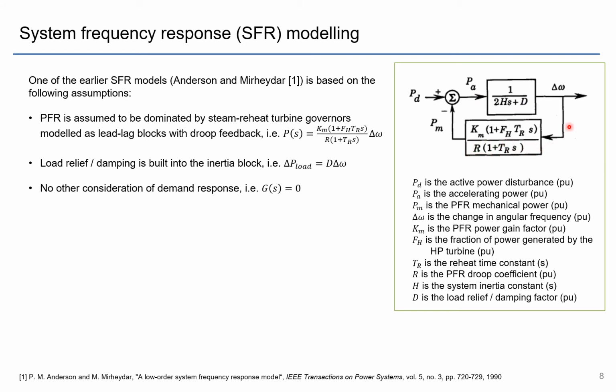So you have here the droop coefficient with the feedback from the frequency deviation. And the PFR itself, you can see, is modeled as a lead lag block. So you have some gain, and then you have a lead component and then a lag component. And that lead lag block is really describing the primary frequency response behavior of steam reheat turbine governors, where there's a short burst of response early on, and then there's a slower burst, which is the lag component. There is no consideration of demand response. So here the transfer function GS is basically equal to 0.